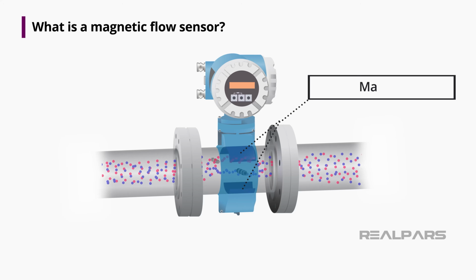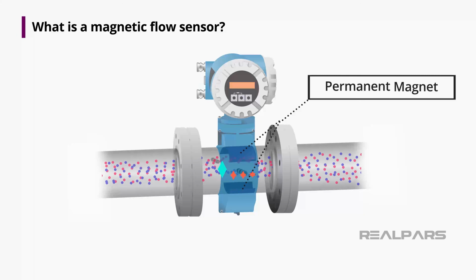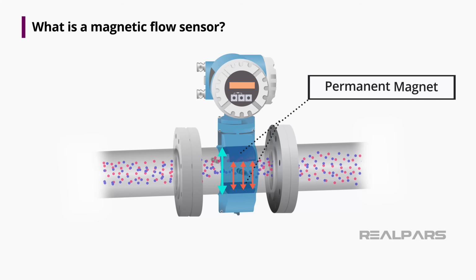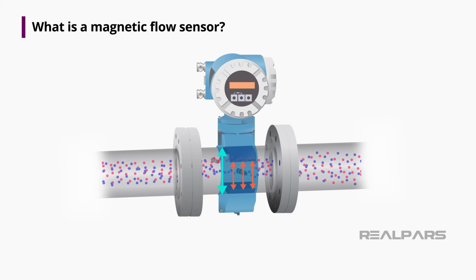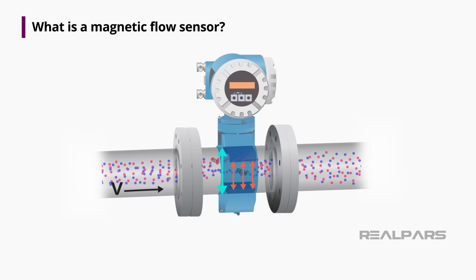The magic that creates the flow signal is based in the magnet. The mag meter is surrounded by an iron core permanent magnet that creates a magnetic field to be established with lines of magnetic flux, which pass vertically through the entire cross-section of the pipe and the flowing fluid. This geometry is very important. The flowing fluid will pass through these lines of magnetic flux at a 90-degree angle, or perpendicular to the lines of magnetic flux.